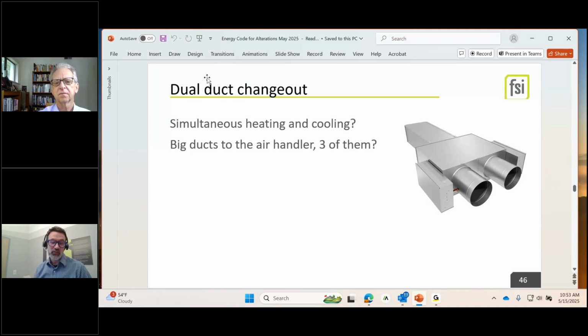So you've got a bunch of big ducts there, and you are not allowed to simultaneously heat and cool in the current code. So you get into a real sticky situation if you're only doing a single zone or a single TI, and you're trying to use exemptions. Pretty exciting. Or you're trying to do what is allowed for VAVs, where you take the cold side air and then reheat it locally. It is no doubt a sticky situation. And sometimes you get out of it just by saying, well, great, that TI we're going to take off of the main mechanical system and put in our own. It's all an if and therefore. But let's just be clear, it's a really horrible system from an energy perspective.